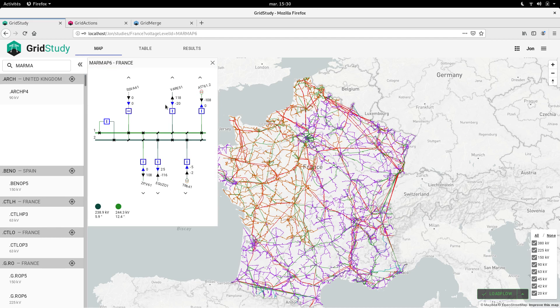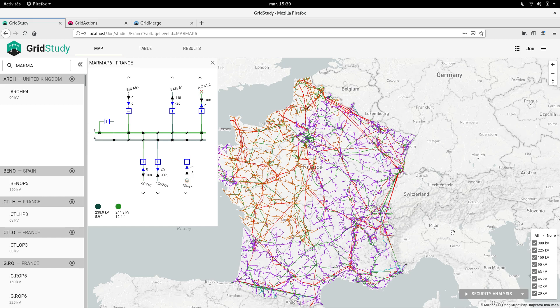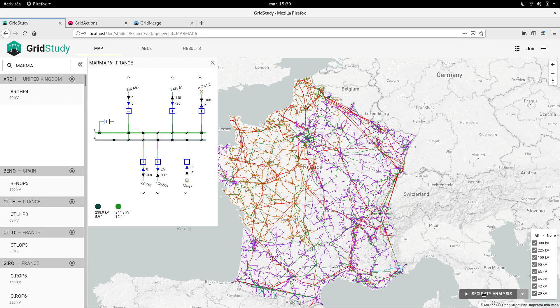Load flow simulations are not the only simulations you can run. Another type is the security analysis. Running a security analysis means checking one by one, for a list of predefined contingencies, whether or not they affect the network. For example, in this case, I could ask the platform to run a simulation in case each of the 400 kV lines in the network had a problem.